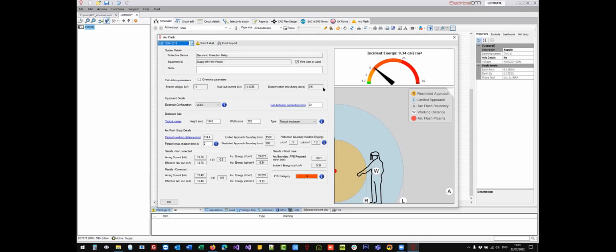Now, from the design, we need the voltage, of course, and the fault levels. And from that fault level, we will calculate the arcing current. Now, from the arcing current, we will calculate then the disconnection time, and based on all these parameters, we will end up calculating the incident energies. Okay, so we have two values here.